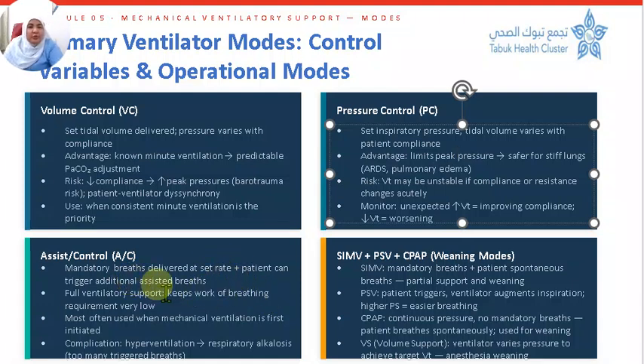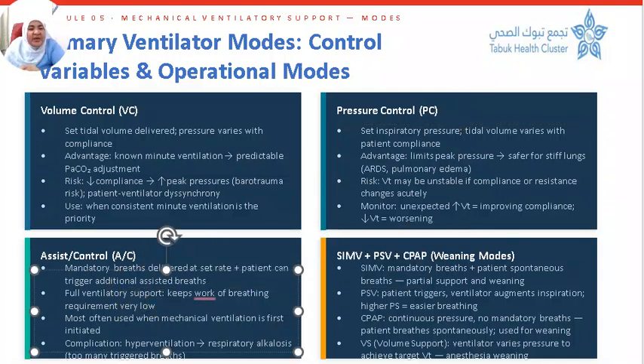In the assist control mode, the ventilator delivers a mandatory breath at the set rate, but the patient can also trigger additional assisted breaths of the same strength. So this is used at the initiation of ventilation when you want to give full support. Now, the risk of this ventilator support is that it triggers too many breaths that can cause the patient to hyperventilate. So if the partial pressure of carbon dioxide drops, pH rises, and respiratory alkalosis arises.